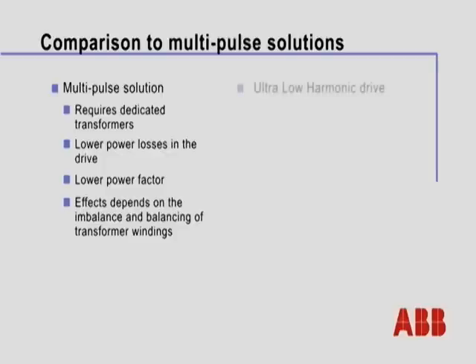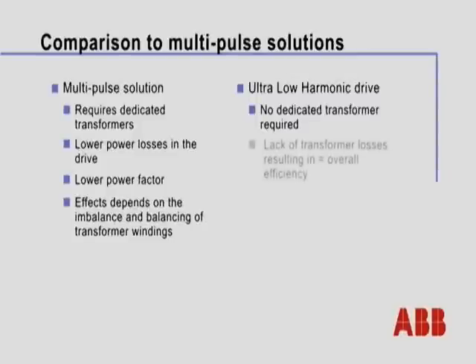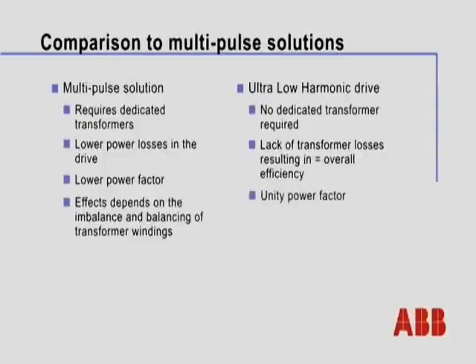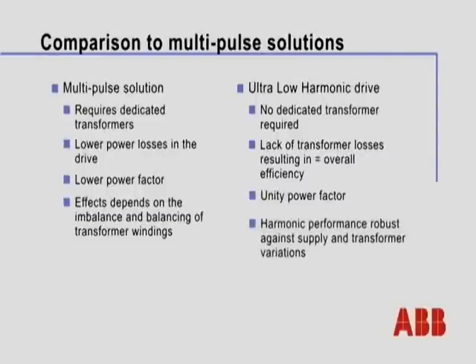When comparing it to an ultra-low harmonic drive, there's no dedicated transformer, no additional hardware, no additional wiring. The lack of these transformer losses, because there is no transformer, results in an equal overall efficiency to the multi-pulse solution. And the ULH drive has a unity power factor. Regardless of what we have on the incoming line or the distribution system, we have unity power factor at the drive. The power performance is robust, and it doesn't matter what the supply or the transformer variations might be, the ULH drive, through the use of its active front end, can compensate for that.